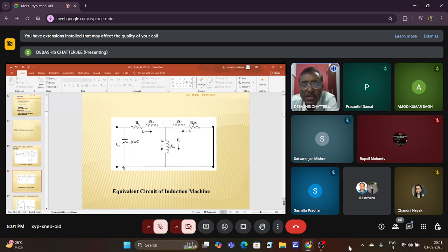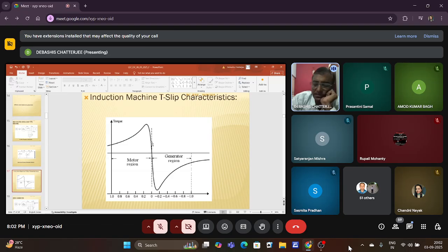Due to the residual magnetism of the rotor, when it rotates, some small voltage is generated at the stator terminals. Now, when the stator terminals have some small voltage, some current will flow through the capacitor, right? The capacitor current leads the voltage by 90 degrees, and the field excitation current, which is actually the inductive current, lags it by 90 degrees. That means you can assume that the capacitive current is supplying the inductive current. So the excitation is generated from the capacitor itself. That is why it is termed a self-excited induction generator, SEIG. This you will see later.